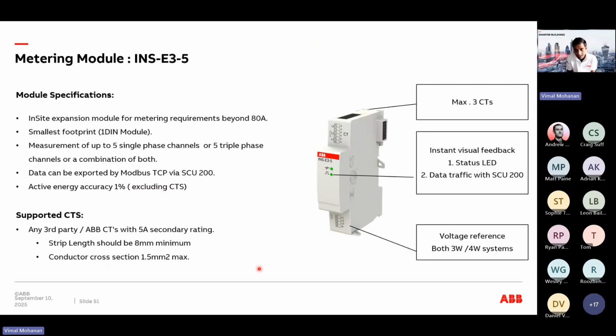Next is the metering module. This is why, when I mentioned the CT connected meters, I wanted to point that out - this is that. If you have a meter, or if you don't have a meter in the project, you can use this module. You've got the L1, L2, L3 in and the CTs. So anything over 80 amps, like we discussed earlier, if you want to monitor it, you can put that in. But that's not to say if there is a meter - of course, if it's got Modbus RS485, bring it back into it. But if it doesn't have a meter, it's a lot simpler to include this rather than putting a meter in.